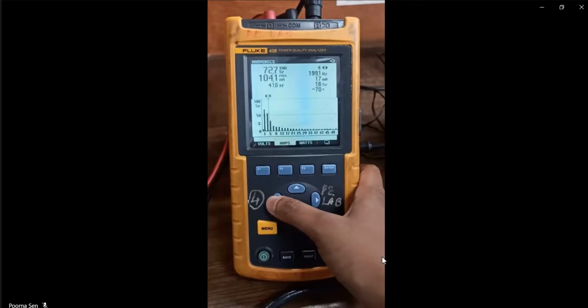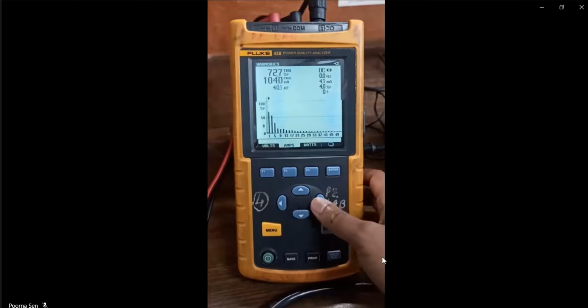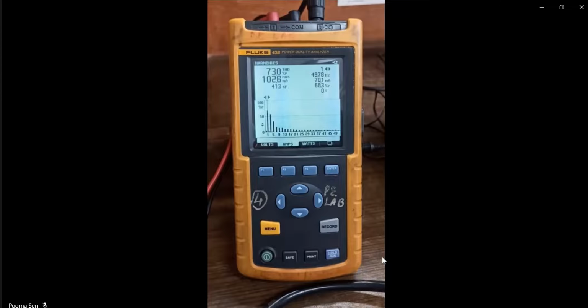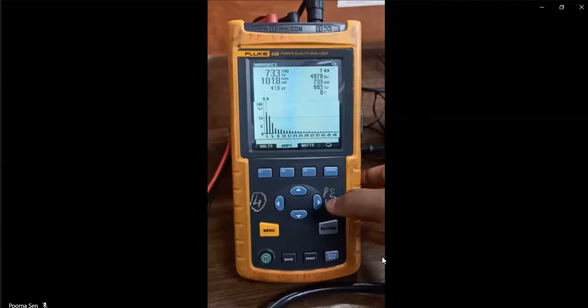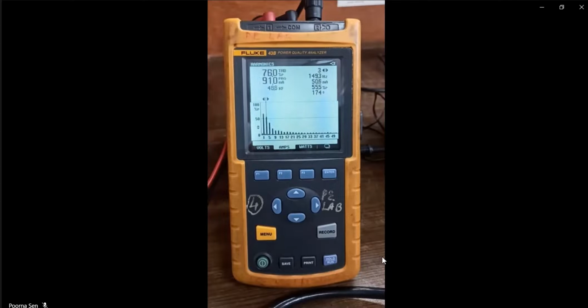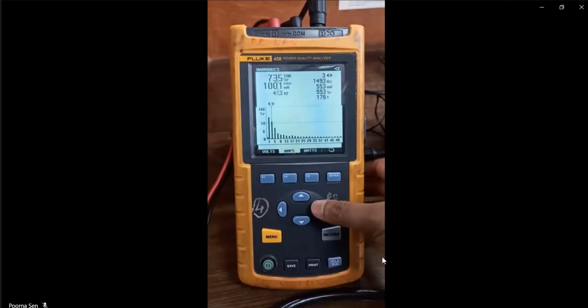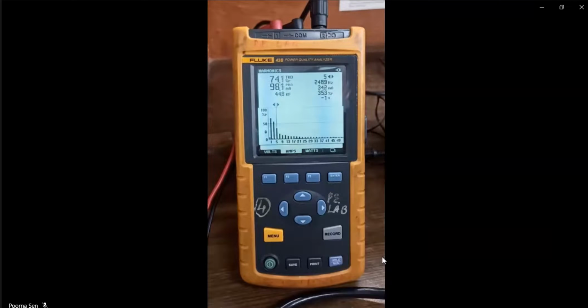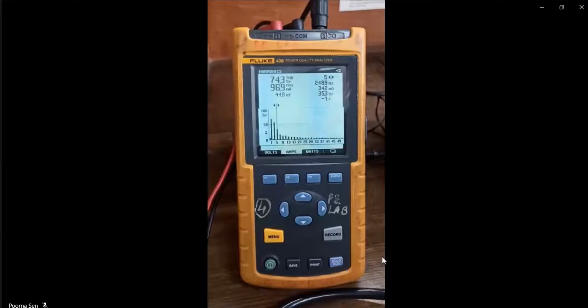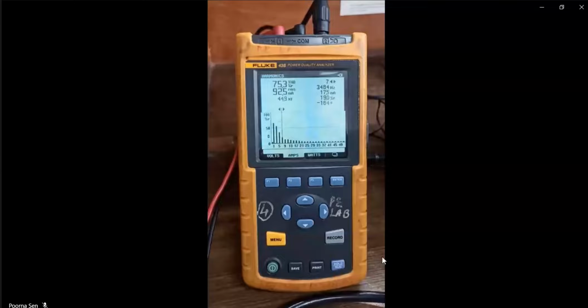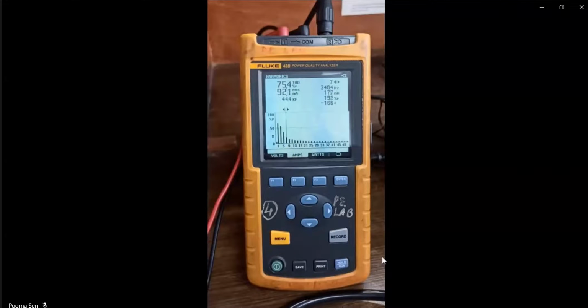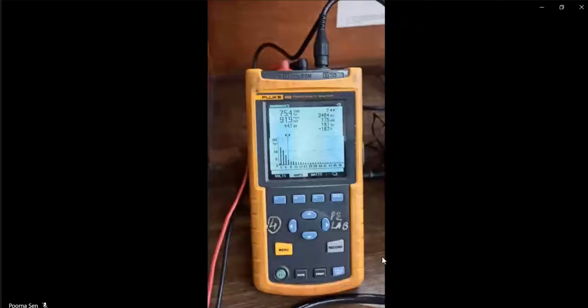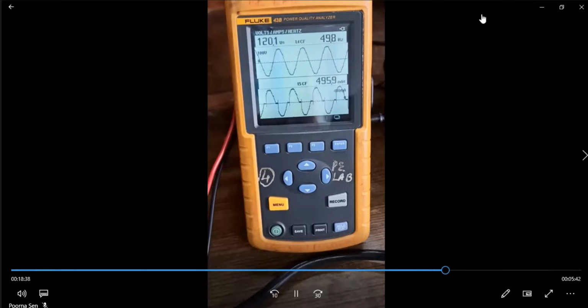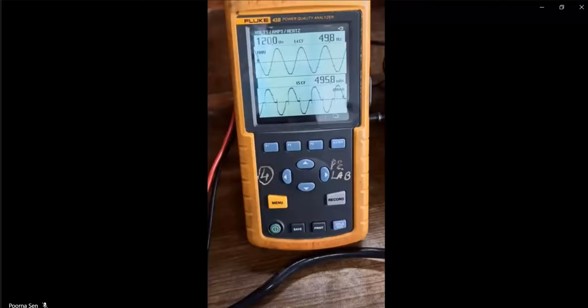THD is 72.7%. First harmonic 69.3 milliampere. Third harmonic 50.6 milliampere. Fifth harmonic 34.4 milliampere. Seventh harmonic 17.5 milliampere. Now we will set the input voltage to 120 volt and again vary the firing angle and take the various readings. We will set the firing angle 2.1 milliseconds.